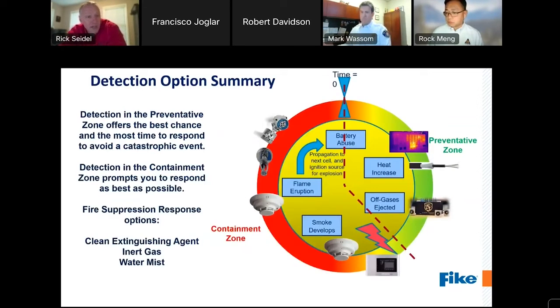To summarize the detection options, we know that thermal imaging, fiber optic linear heat detection, or off-gas detection keeps you in the preventative zone and offers the best chance and the most time to respond as quickly as possible to avoid a catastrophic event. Whereas detection in the containment zone, which is your traditional spot type smoke or heat detection, and even air sampling smoke detection, as well as flame detection or a sprinkler head to offer heat detection, basically just prompts you to respond as best as possible to try to help contain and protect the surroundings.